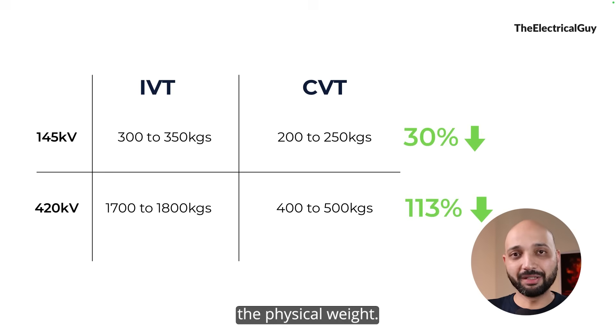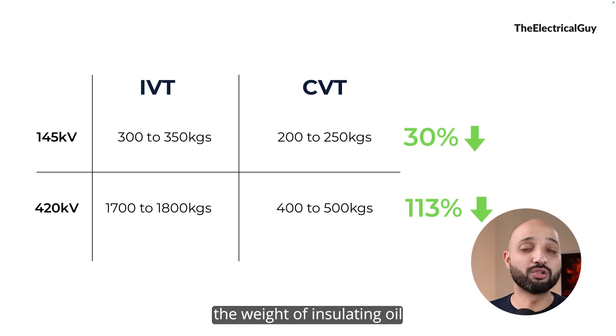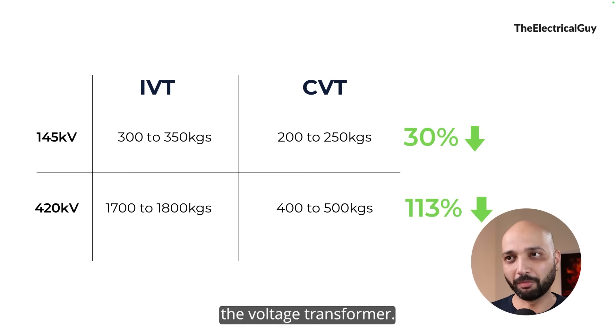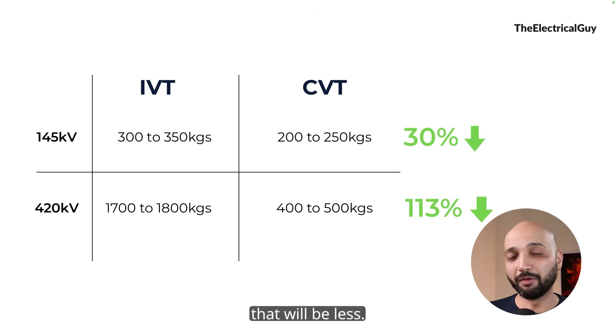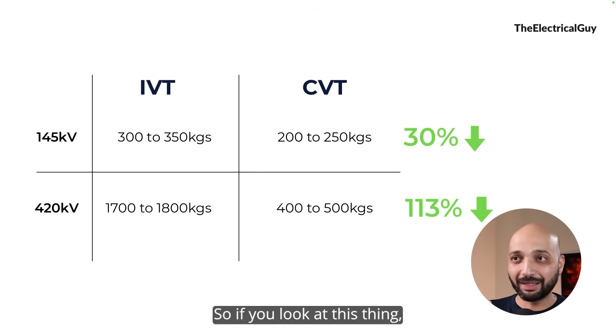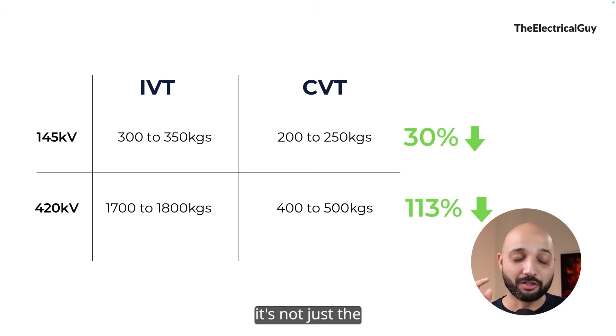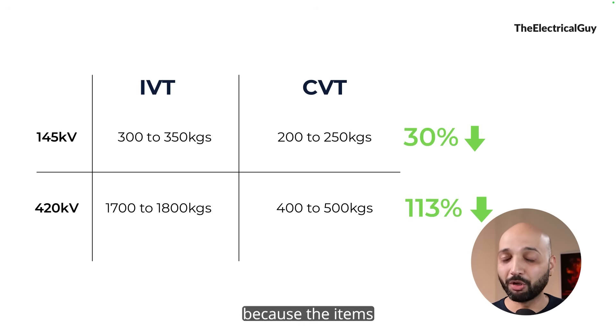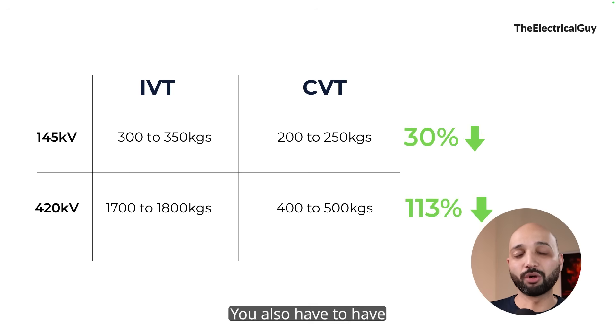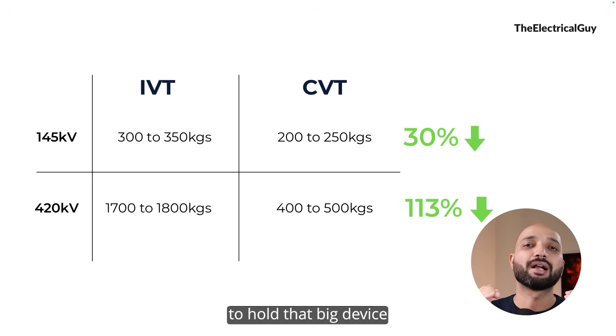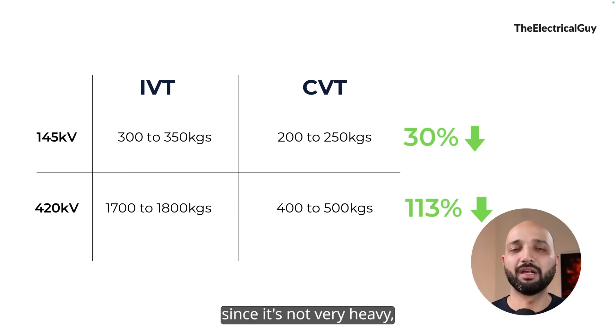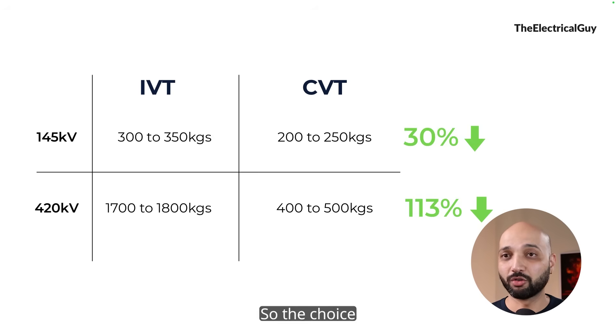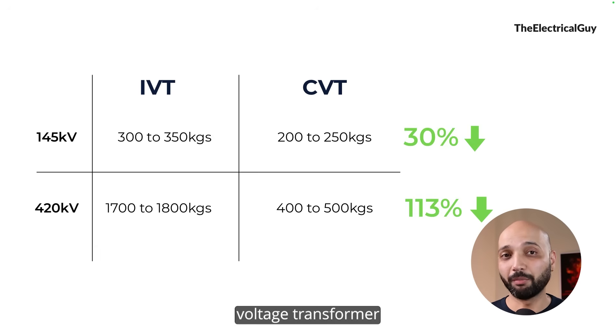This weight difference is not just about the physical weight of the device — it also includes the weight of insulating oil used inside. IVTs need more oil to provide more insulation, whereas CVTs need less. Furthermore, because IVTs are bulkier, you need a stronger support structure to hold them, whereas CVTs, being lighter, can be supported by a regular structure. The choice of support structure also varies based on the type of voltage transformer.